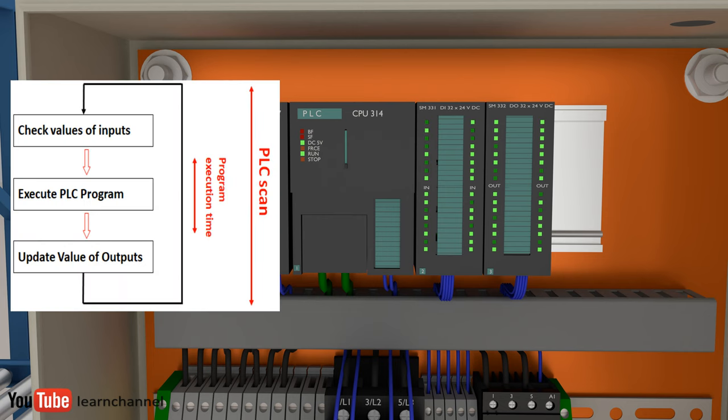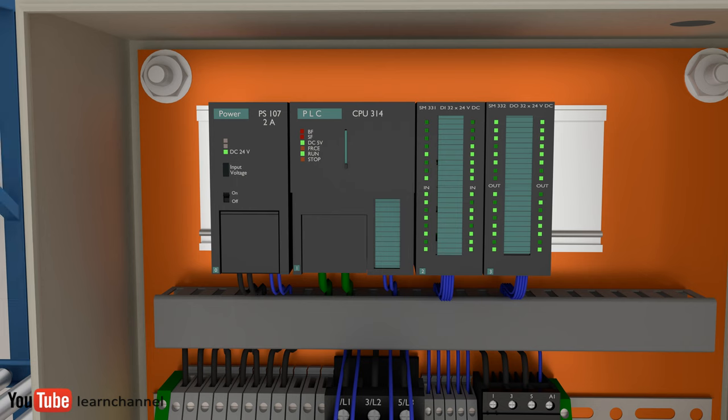In this context, two terms describe the speed of the PLC. The program execution time is the time required by the PLC for a single execution of the program. The total response time taken by the PLC to read the inputs, solve the logic, and write the outputs is called the PLC scan time. Consider that a big user program will increase this time. Take both times into account if you have to plan control with a PLC, especially for time-critical tasks.